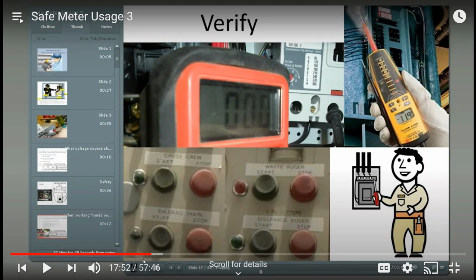Go ahead. So yeah, most of the time, where I'm coming from, you're only ever going to have the meter set in two places. You're either checking ohms with all the power off, or you're checking voltage, and obviously you'll have to have power to be checking voltage. Or sometimes you're looking for the lack of voltage. True, true, absolutely true.